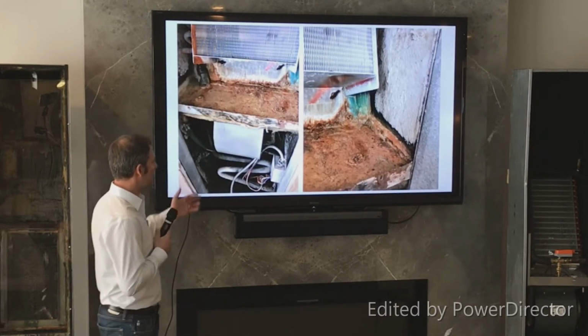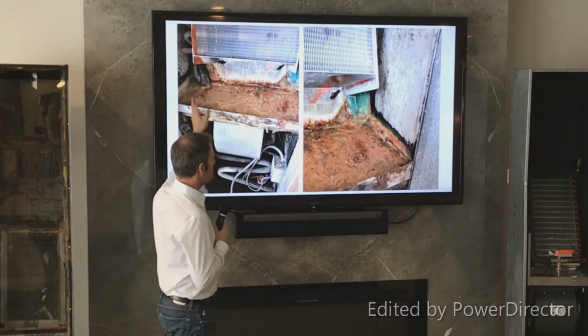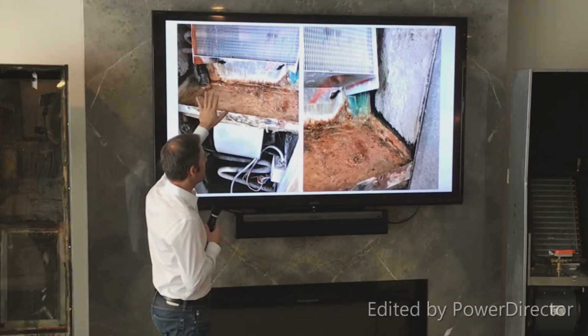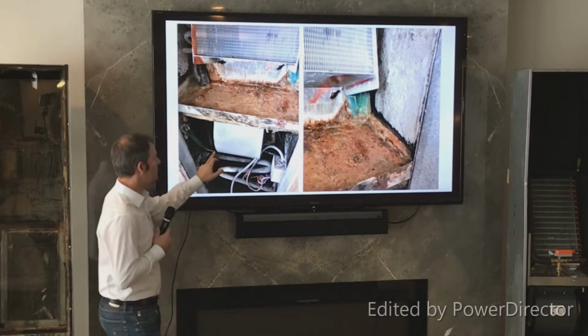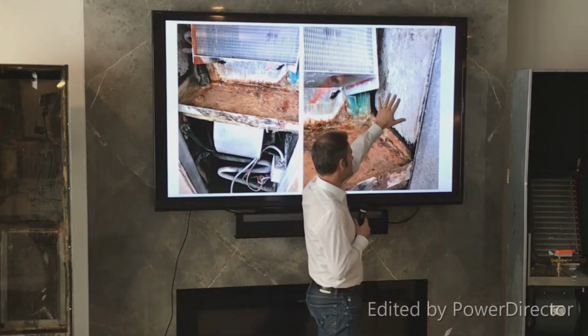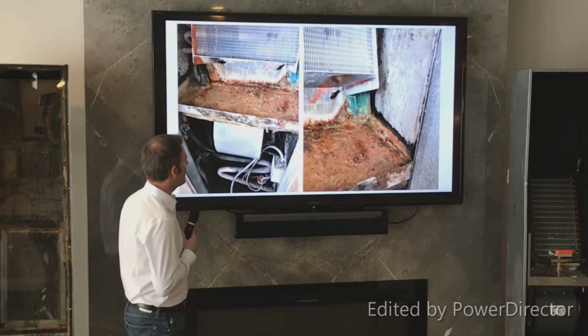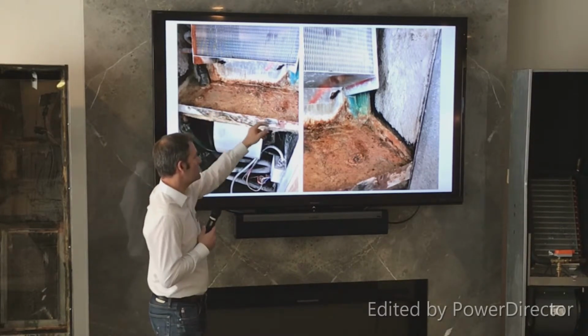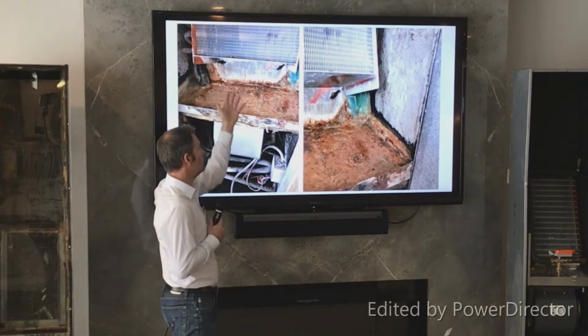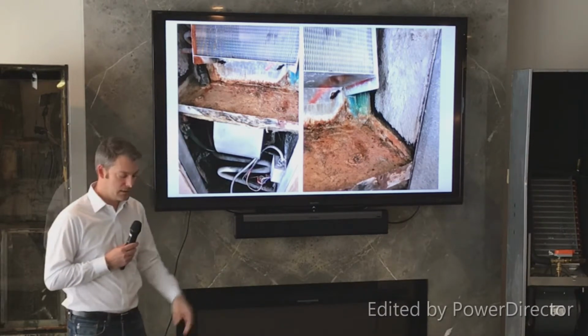And this is why. Here are two shots of a drain pan in a 30-year-old unit. As you can see, the pan is completely rusted over. There's lots of flaking, so any of those flakes can cause a problem by getting caught in the drain hose, or like I mentioned earlier, this insulation can begin to flake, or the mold can flake and also fall into the drain pan, and then flow down into the drain hose and cause a backup. On top of that, as this flaking happens, pinhole leaks can develop in the drain pan as well, where the water would come off the coil, flow into the drain pan, and not make it to the hose, but just drip right through the pan because of a severe amount of rusting.